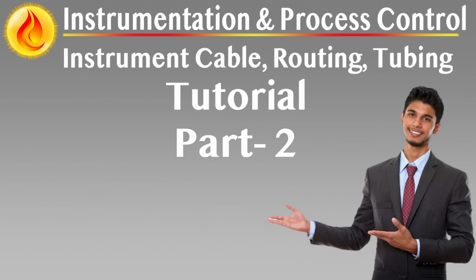Junction boxes for multi-core pneumatic tubing. Pneumatic junction boxes provide a consolidation point between field devices and multi-core tubing bundles. They must be installed in accessible low fire risk areas and located as close as possible to the connected instruments to minimize single line lengths, ideally not exceeding 15 to 20 meters.